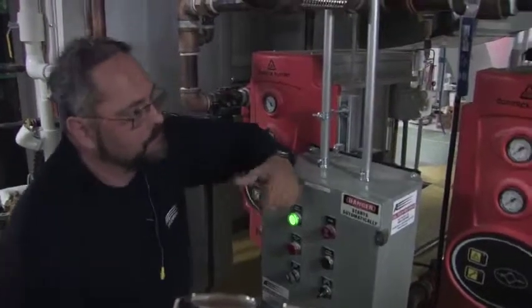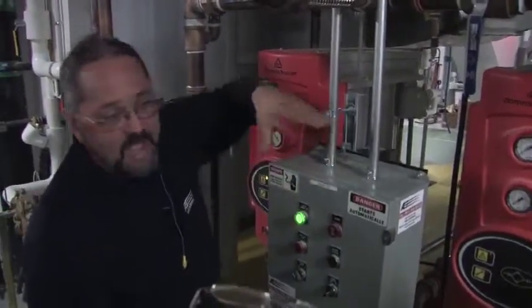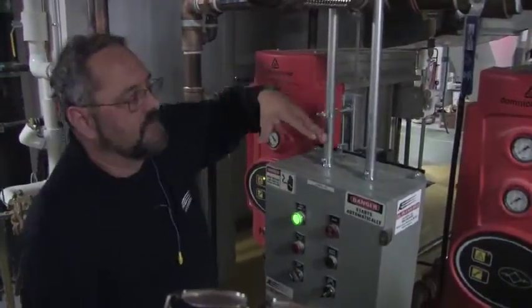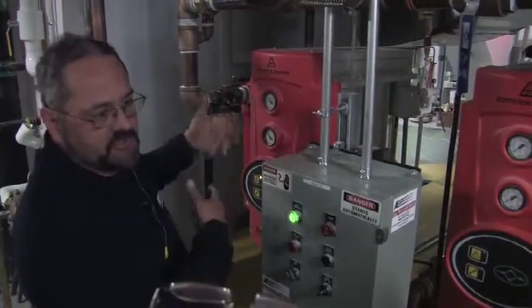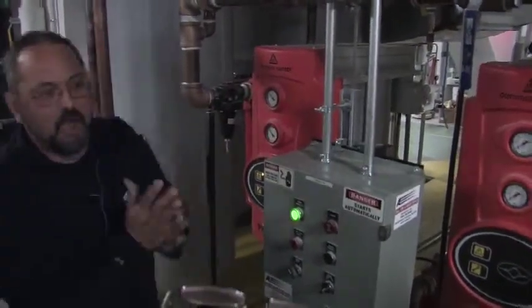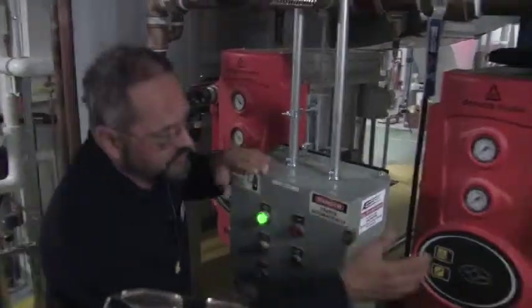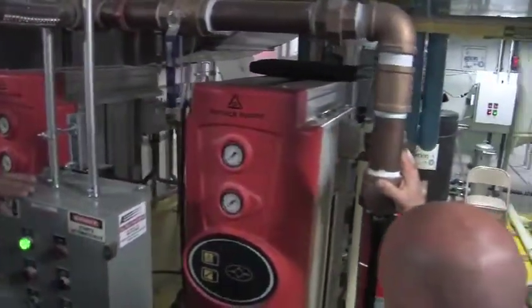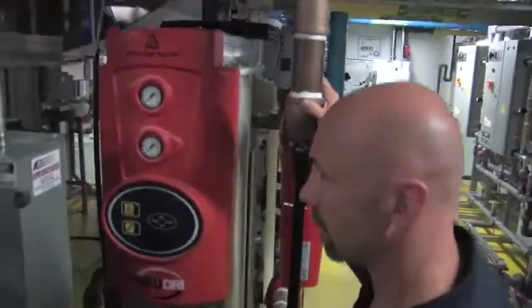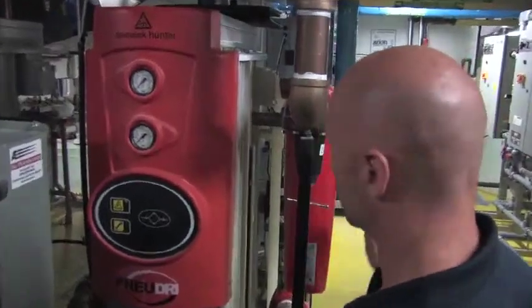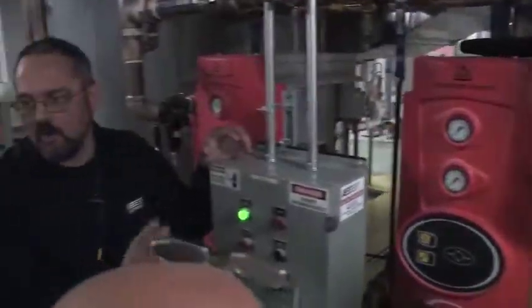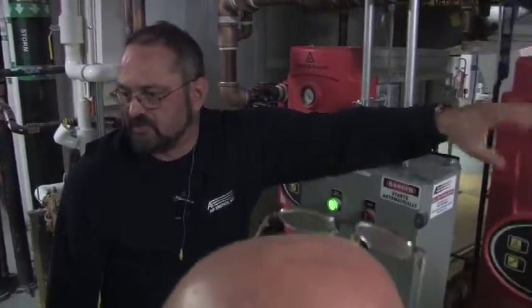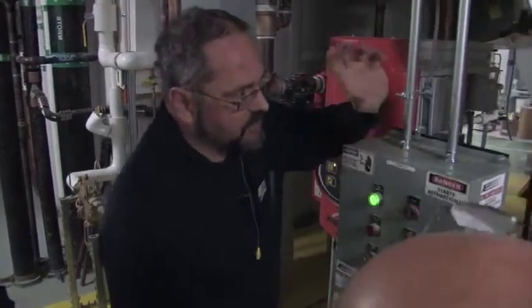At some point we're going to have to change them, I guess. Eventually you have to either add to them or change them, because every time the thing recharges, it's crushing some of those beads. They rub together, and that's what this filter's for. If you notice, the other ones have an auto drain on them. This just has a manual drain. You should never see any water at that point. That filter is to catch the dust that comes off the beads before it goes downstream. This is the final filter, it catches the dust.